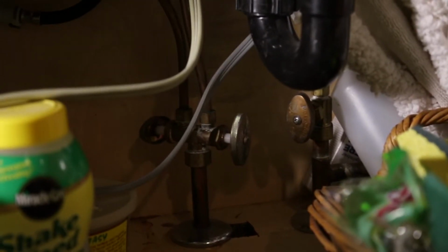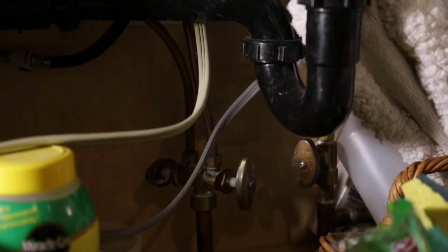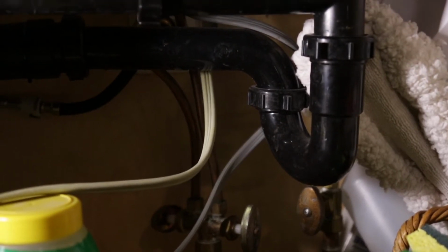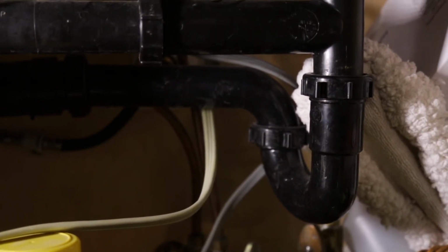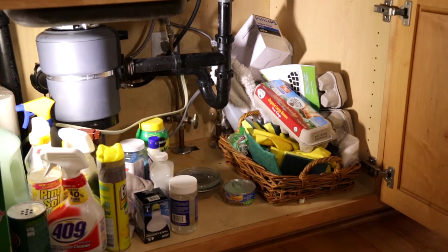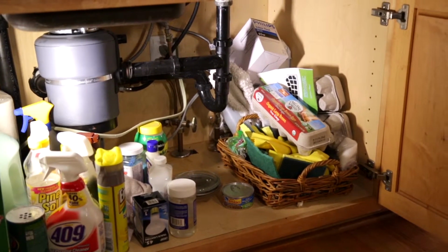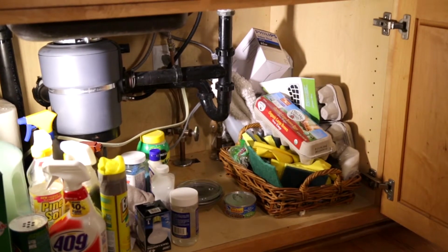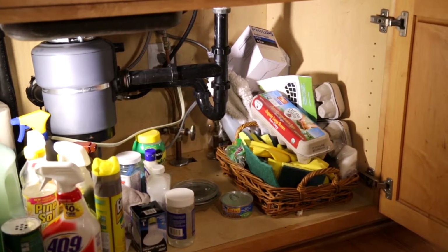But we did find that part of the current has come over to the kitchen cabinet and to the garbage disposal and the dishwasher. So you recall my telling you that current flow on the grounding system takes all available paths back to the power company, and it wouldn't just stop with the refrigerator if there was another good path to take back to the power company.